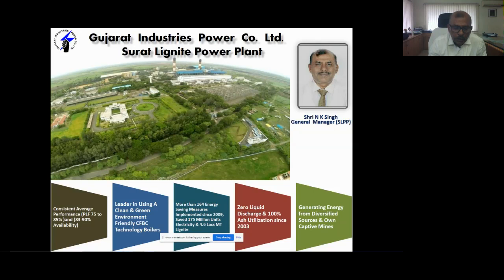We are using clean and green, environment friendly circulating fluidized bed combustion technology boilers, basically for firing low grade fuel, that is lignite, having moisture content of 43 to 52% and sulfur content in the range of 0.6 to 1.2, though it is designed for 2% sulfur content.